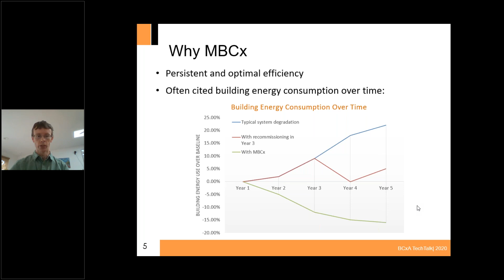EMIS really offers much deeper analytics of building operations than we've ever had before with all this data. We've talked a little bit about energy tracking. The anomaly detection is, if you have equipment suddenly using more energy than was being tracked before under the same outside air conditions, then that would be flagged, and you can immediately jump on that and correct the issue, so you don't have a long-term impact of something operating incorrectly hitting your bottom line on your utility bill. The fault detection and diagnostics plays into that.